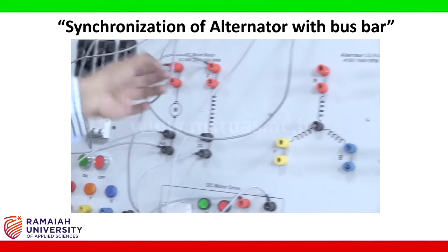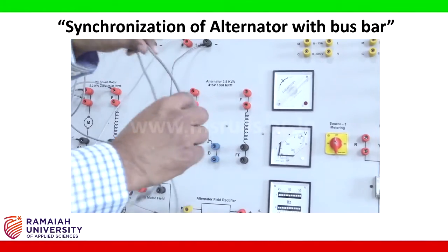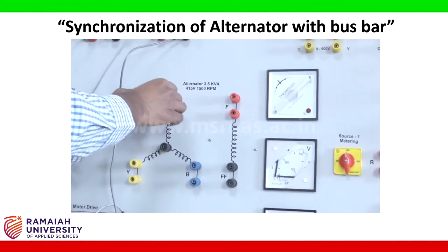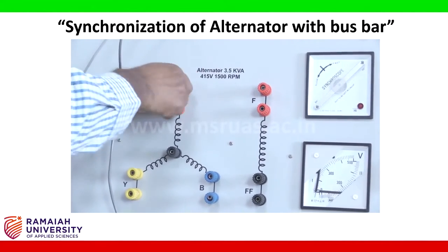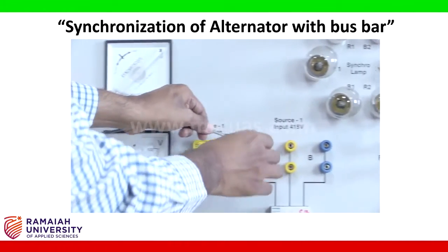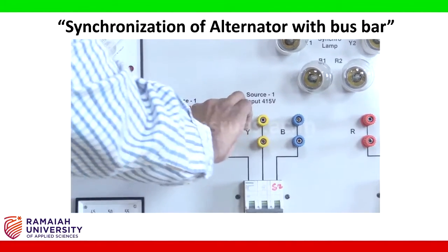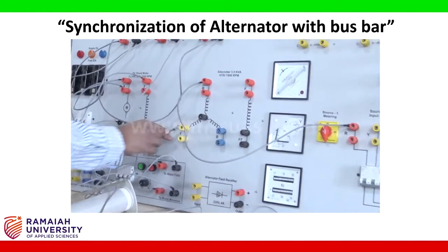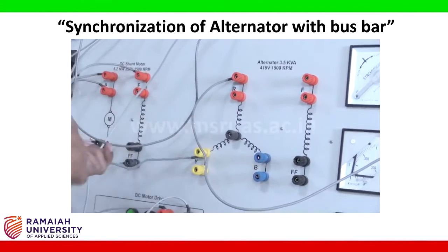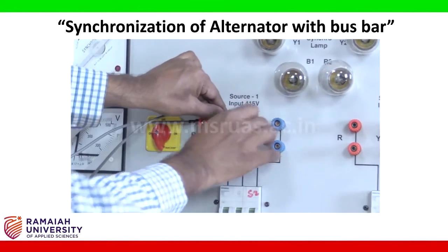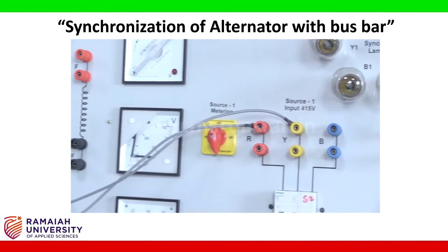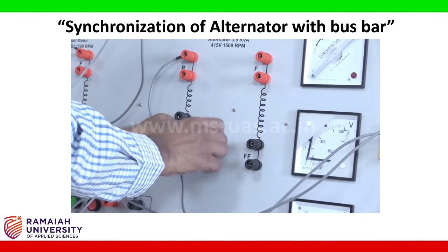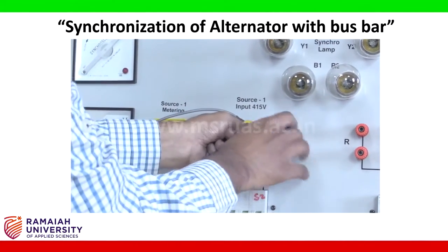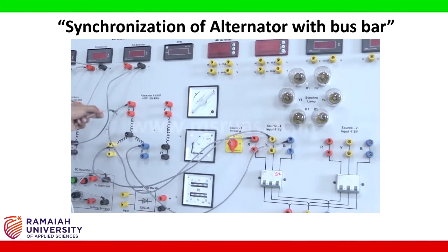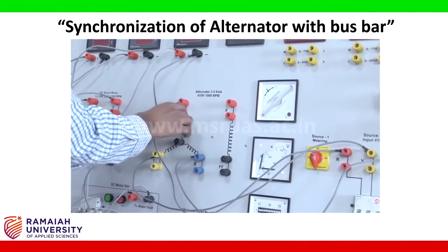Now we will connect the alternator connections. Take one wire and connect from R terminal to R terminal on the synchronizing panel. Take one more wire and start connecting from Y terminal to the Y terminal of the panel board. Take one more wire and connect from B terminal to the B terminal of the panel board.